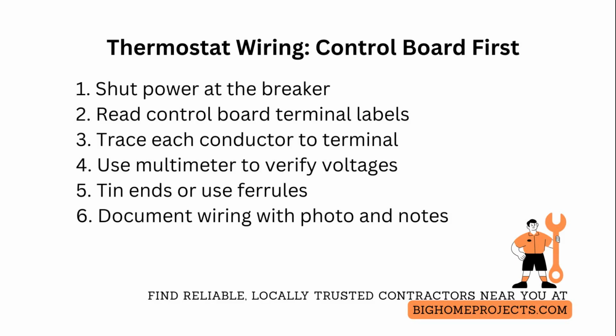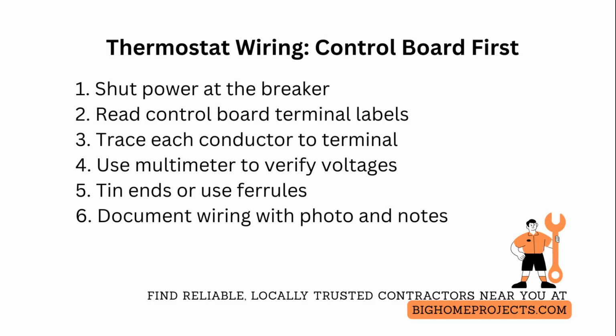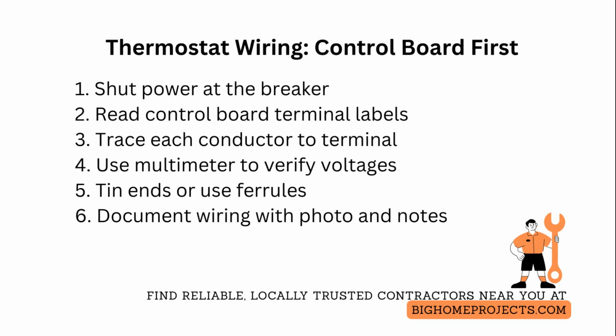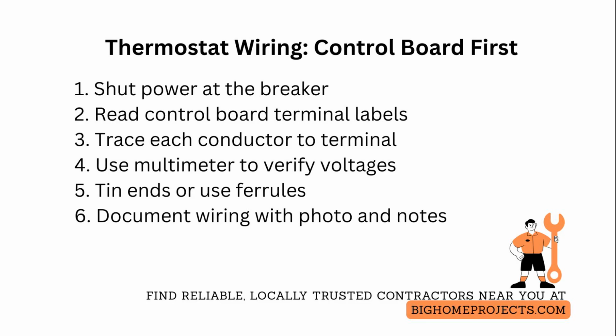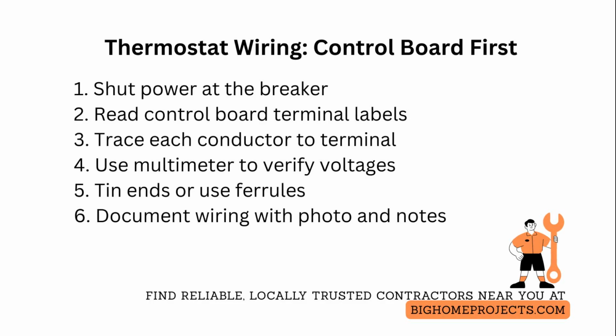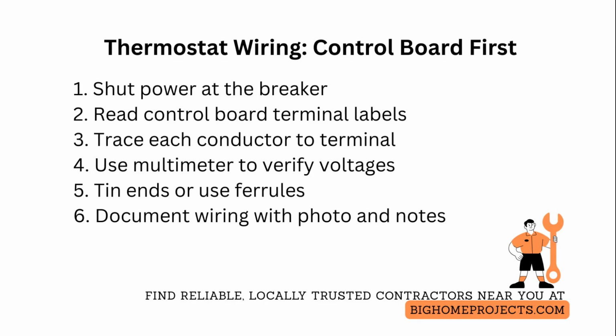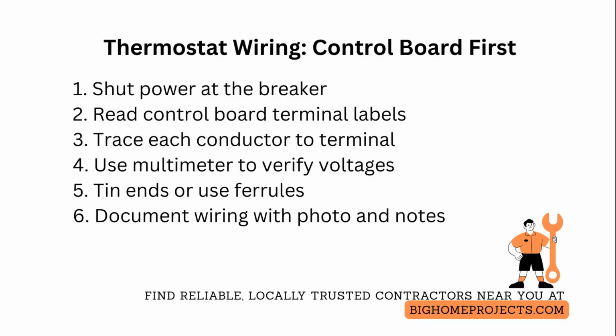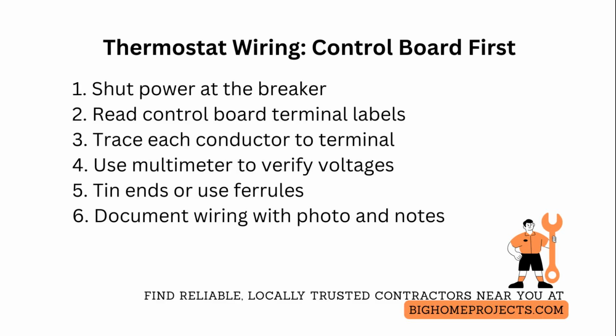Read the terminal labels directly, R, C, W, Y, G, and any auxiliary or heat pump specific posts, and trace each conductor to confirm which terminal it actually lands on rather than trusting wall color codes. Use a digital multimeter to verify that the R terminal has 24-volt alternating current relative to the C terminal and that switching circuits W for heat, Y for cooling, G for fan are low voltage control circuits that close to R when called. If dealing with a heat pump, identify reversing valve and strip heat terminals by locating O or B and the auxiliary heat relay.